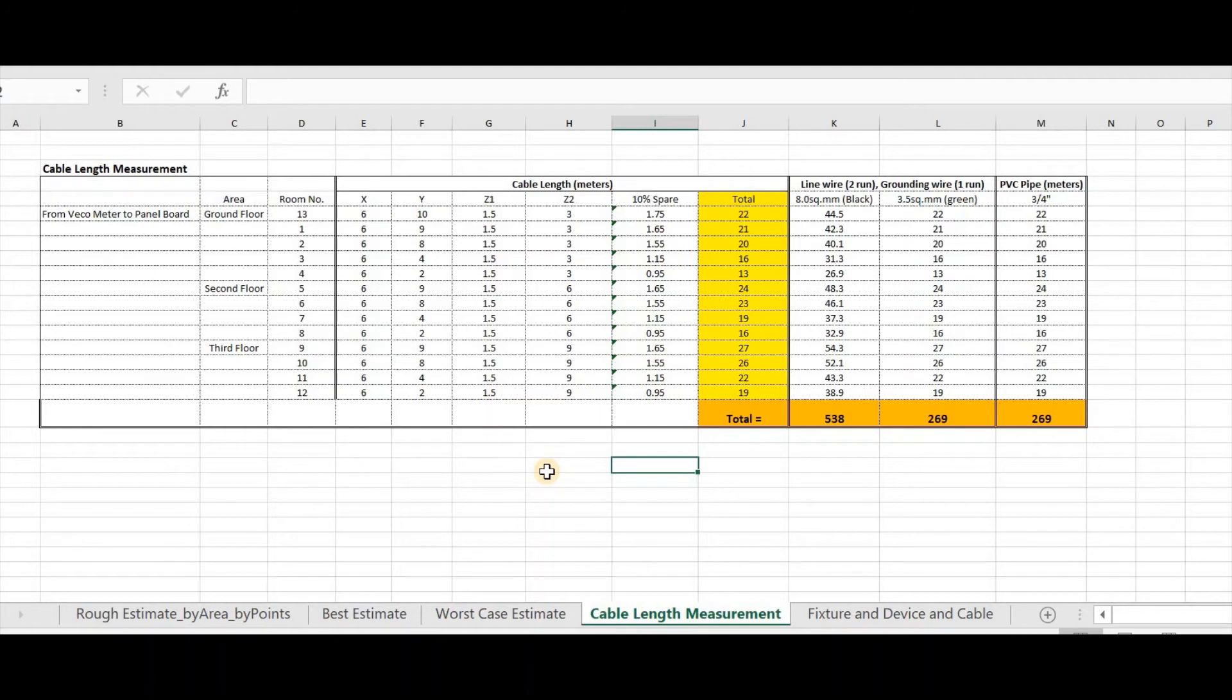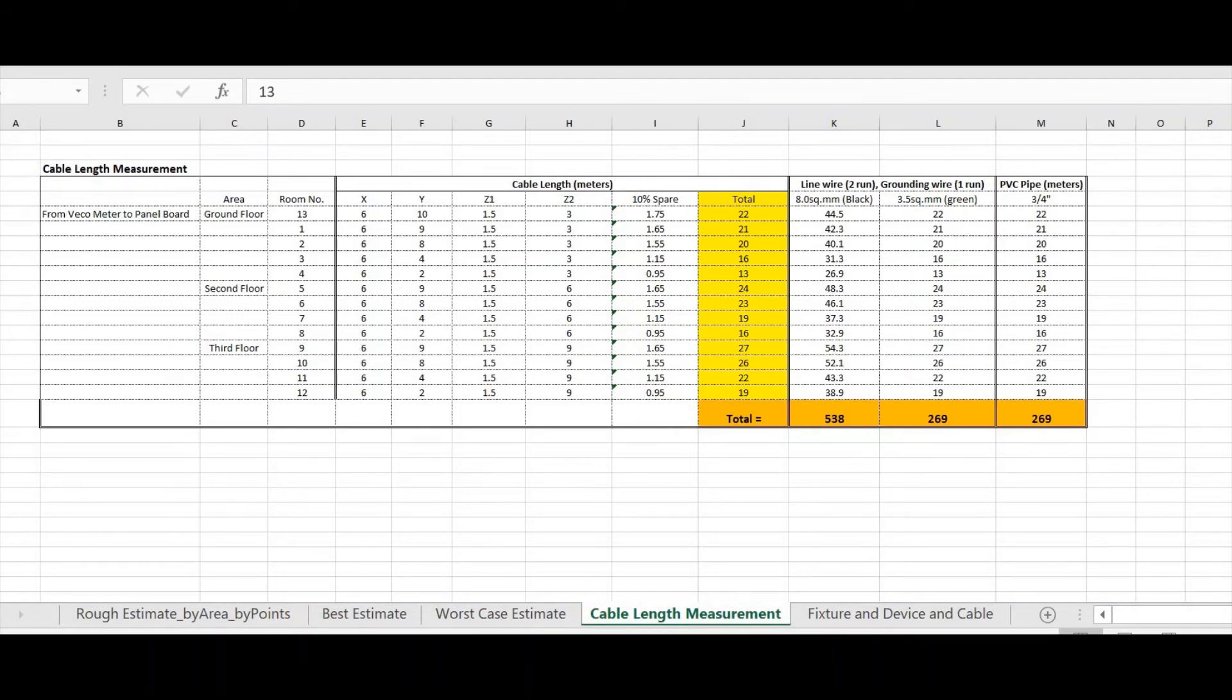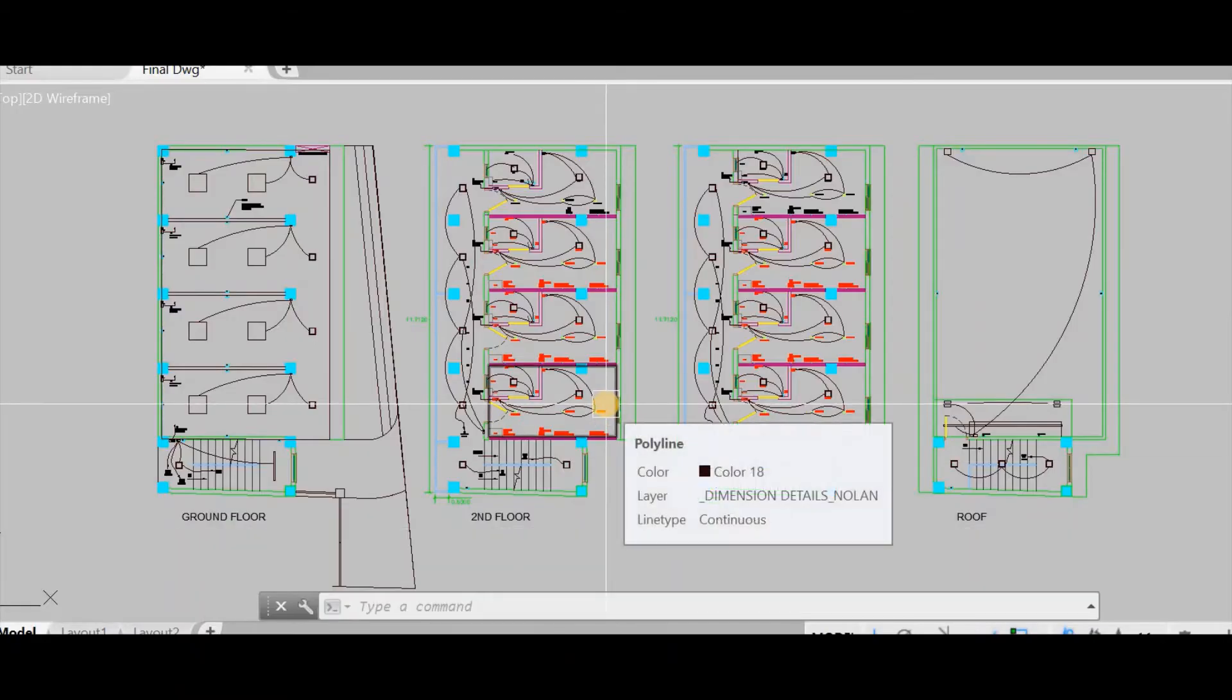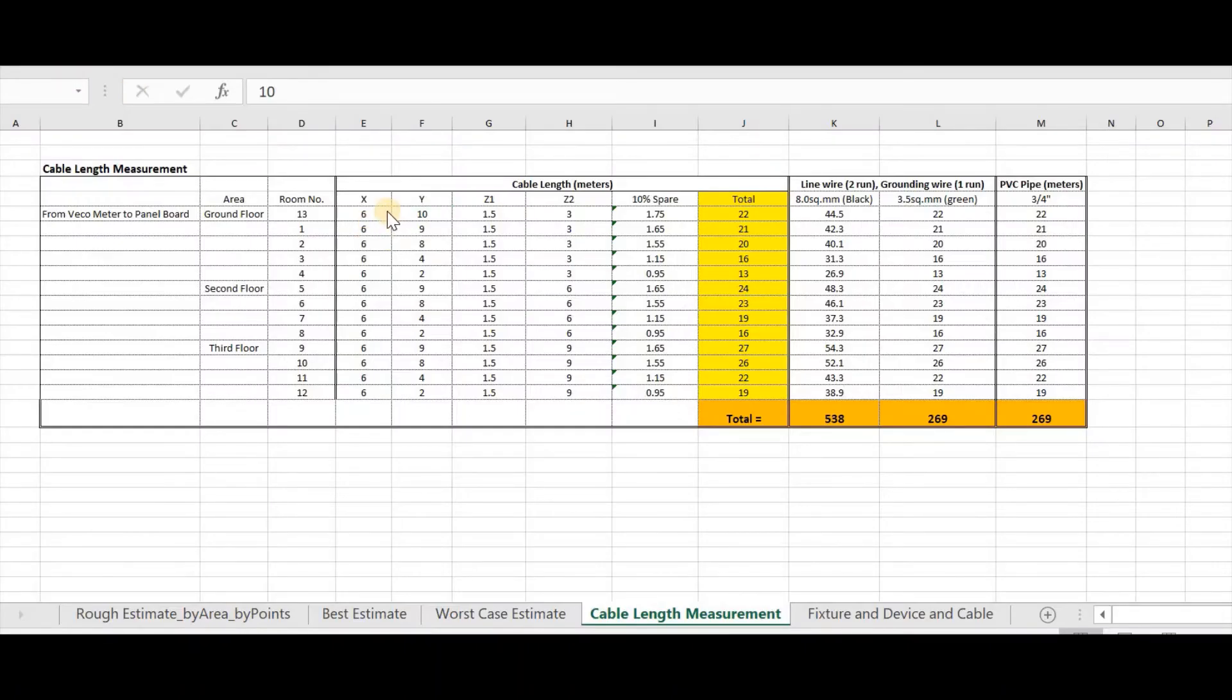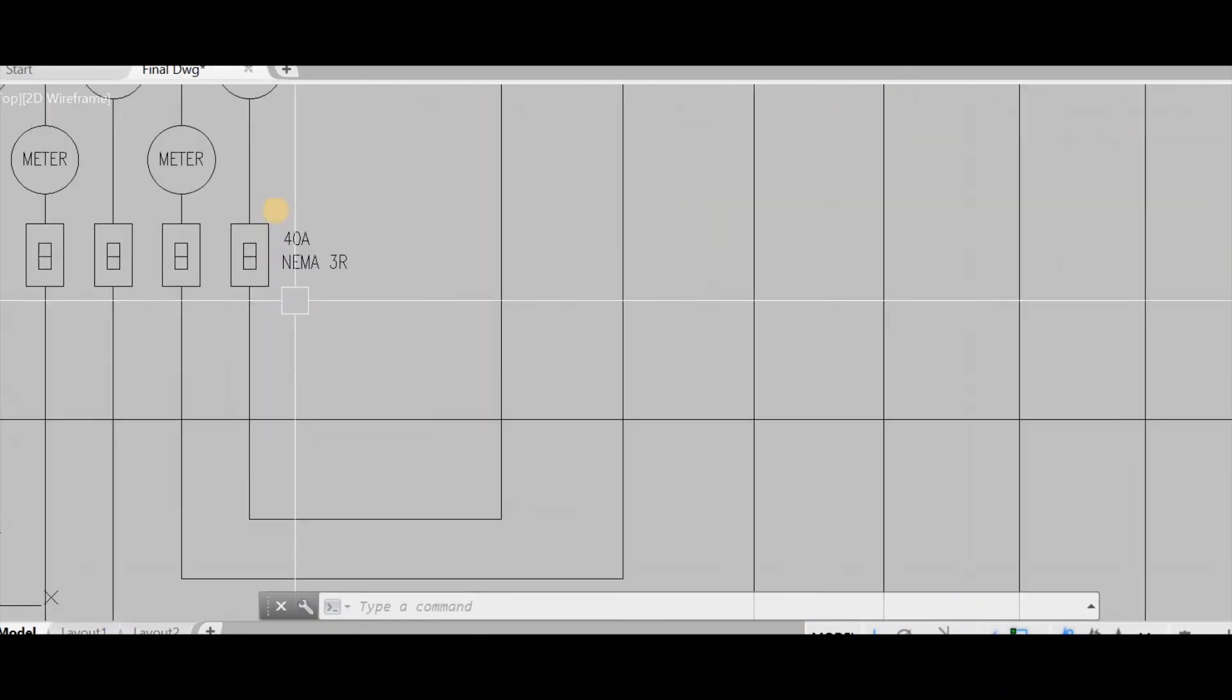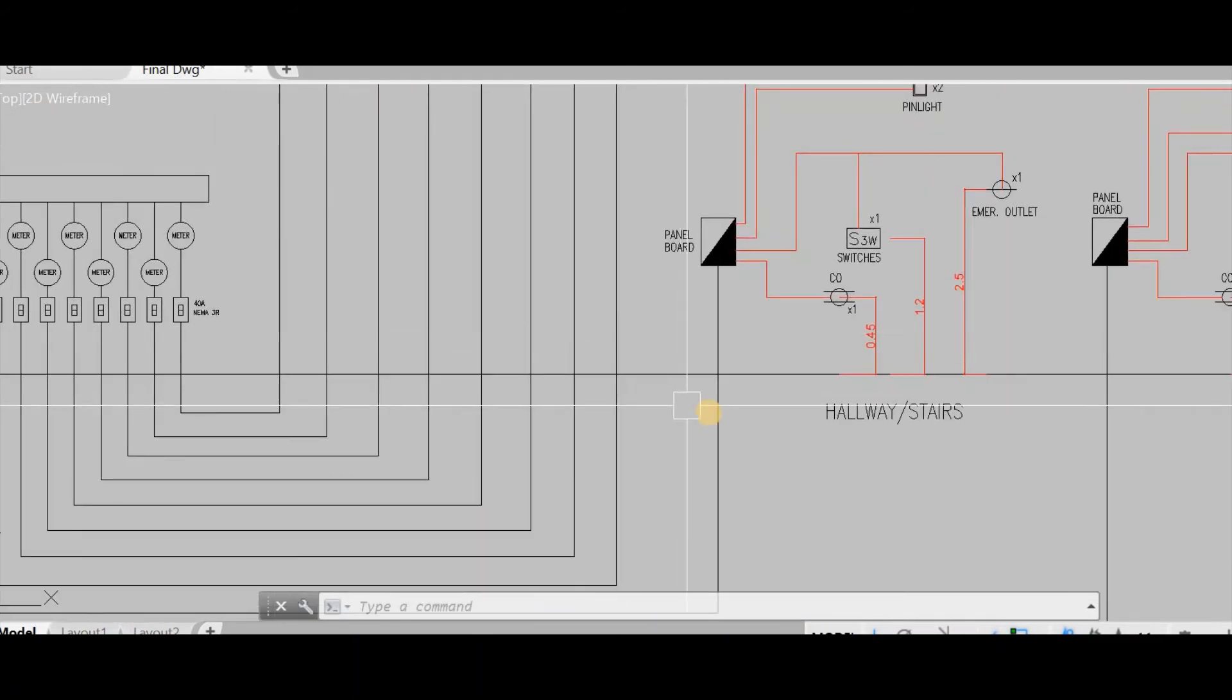Let's have an example. In this cable length measurement, I want to measure wiring from Veco metering going to panel board. In ground floor, we have room number 1, 2, 3, and 4. To determine the X and Y length, we need to go to the layout drawing. So, this is X and this is Y. Back to our format. Our X is 6 meters, our Y is 10 meters. To determine the Z, we need to go to our riser diagram.